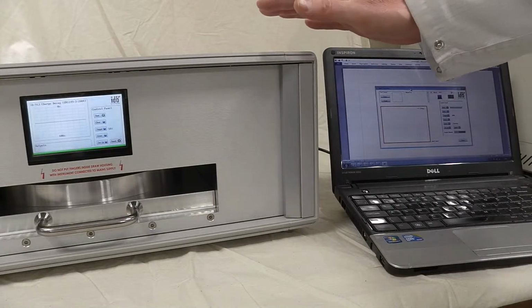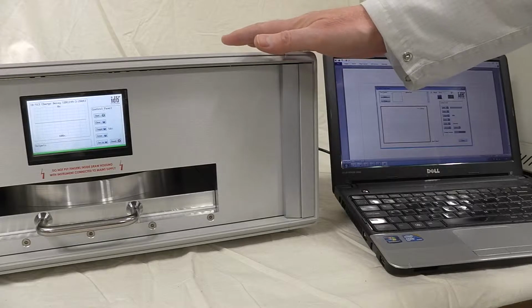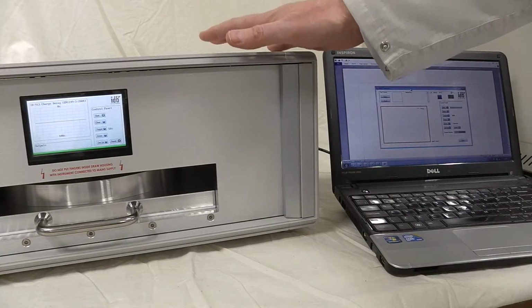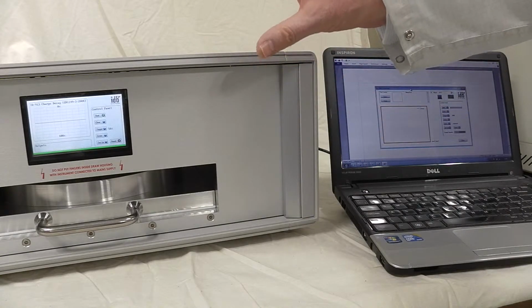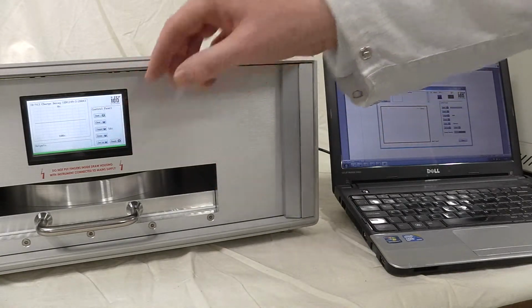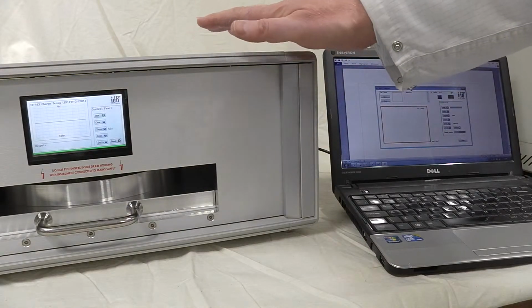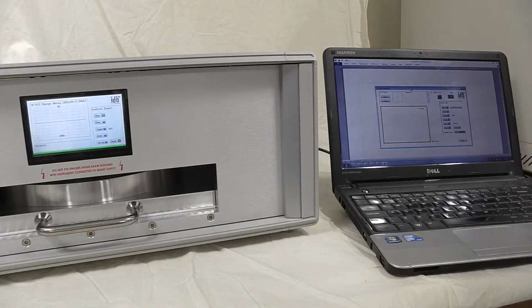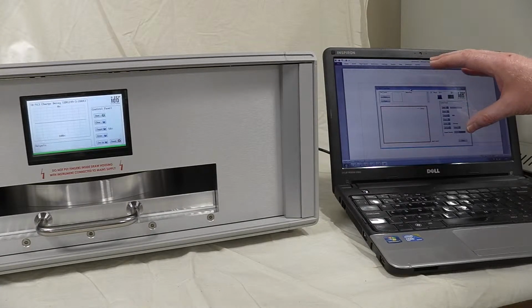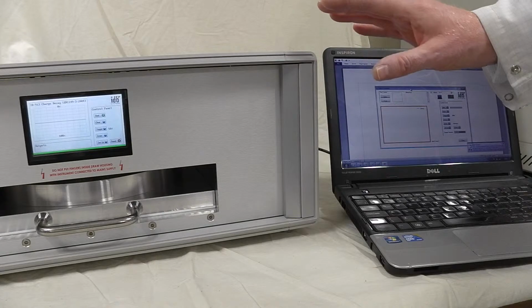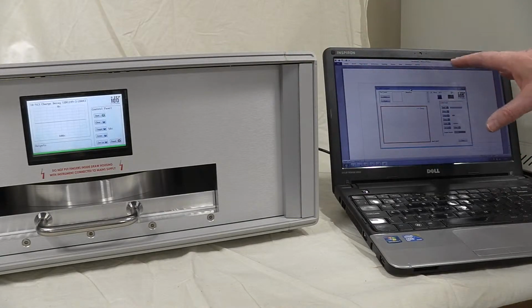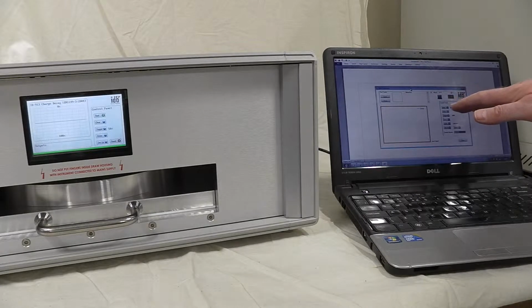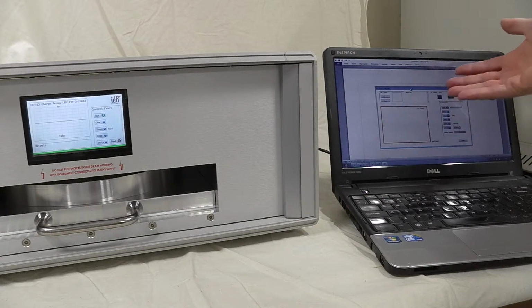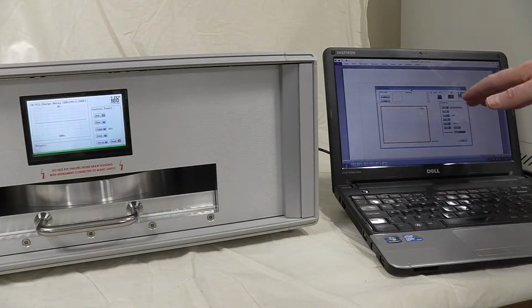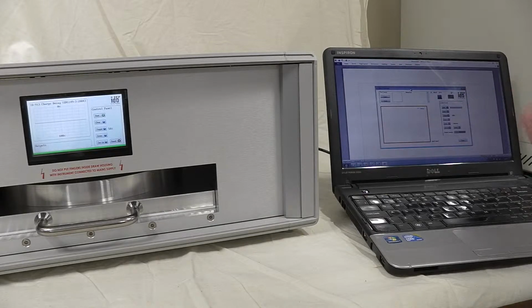So we've previously demonstrated the ID-913 charge decay meter operating in a standalone environment where the instrument controls the test voltage, makes the measurements, and it's all done via the TFT touchscreen display. Now we're going to demonstrate using the instrument with, in this instance, a laptop, and the laptop's running a simple GUI that we've developed here at IDB to control the instrument in exactly the same way, but with the added advantages of being able to store the test results on the PC so that you can analyze them later under a sample number, so you can start allocating numbers to your test samples.